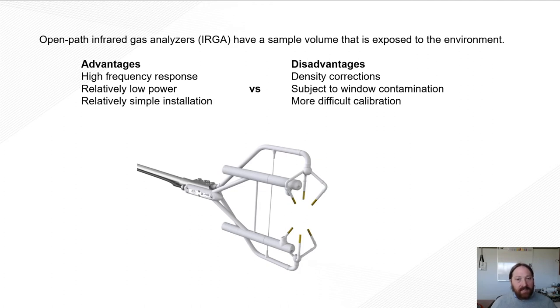The open path is also subject to window contaminations. So because it's exposed to the environment, bird droppings or rain or other contaminants can get on the windows and affect our signal strengths. Now we calibrate for this in the factory, but when things aren't spectroscopically flat, we can't account for that, and we can get errors in our measurement.